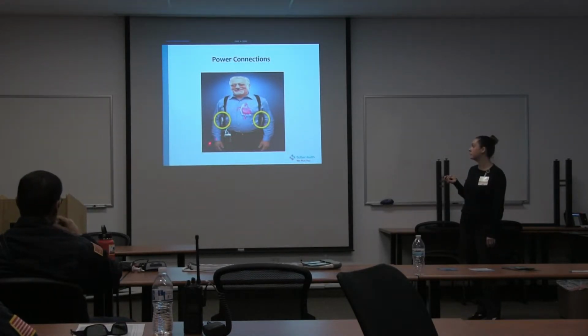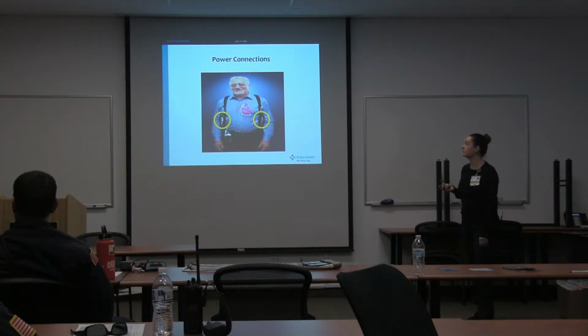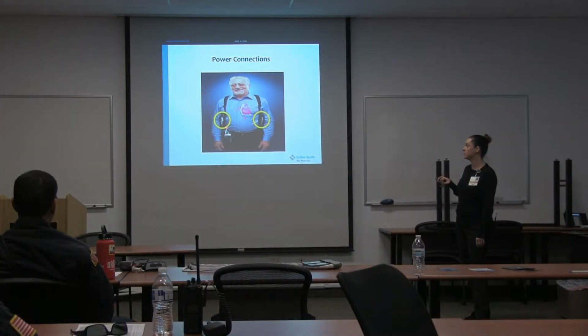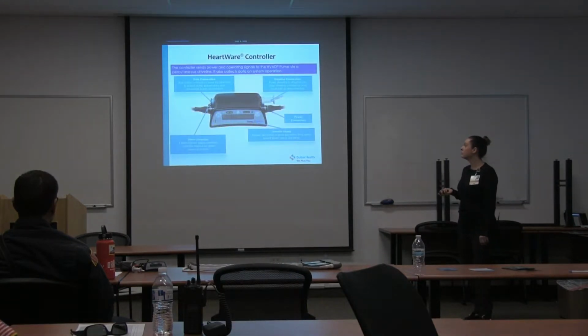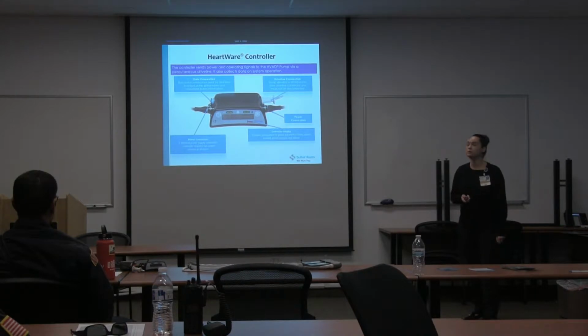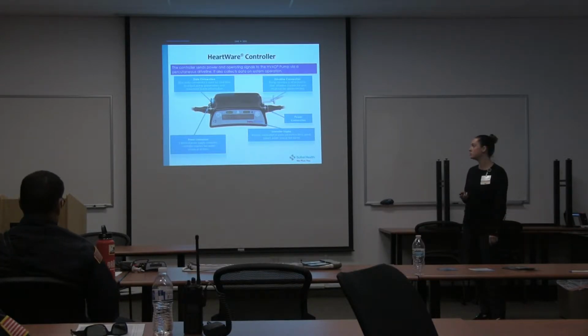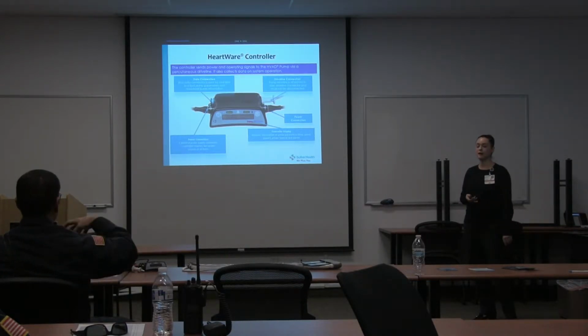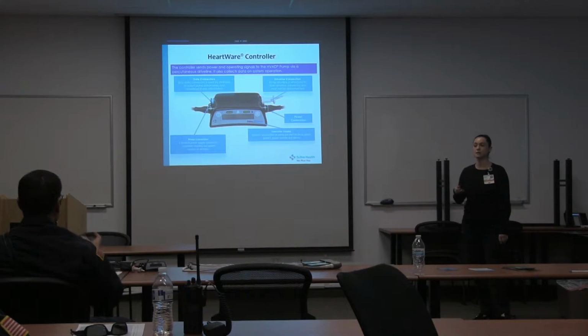They have their computer here that's attached to the driveline inside the body, and then the power sources are connected to these batteries that are connected to clips. So the clips allow that flow of electricity from the battery to the clip to the controller. For the HeartMate device, same idea. They have an LCD screen that interacts with you, that tells you if the patient is having an active alarm. It'll give you a message on there that you can read what the problem is, what the action is. For instance, if the patient doesn't have power, it'll say power disconnected, connect power.